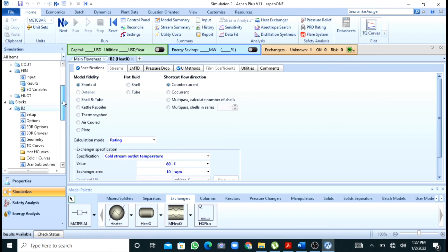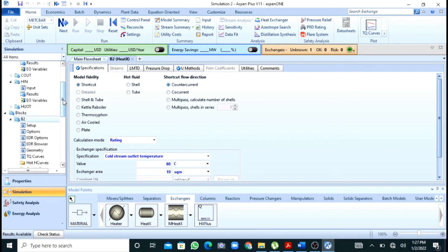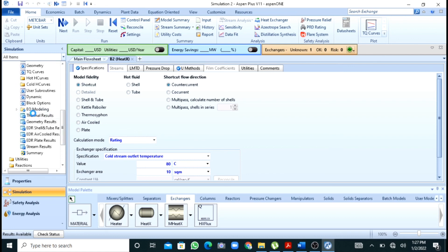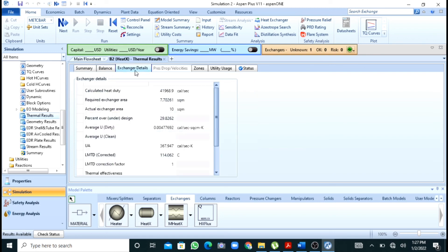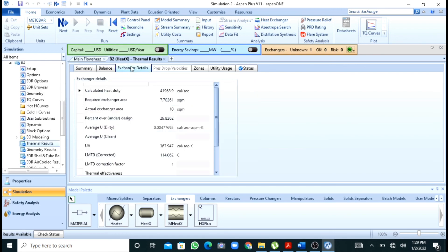The results are now available. I will press Thermal Results — you can see that the hot outlet stream temperature is 128°C. To find the required heat transfer area, I will press Exchanger Details. Here you can see the required exchanger area for this heat transfer to happen. The heat duty is also calculated and you can change units as required. I hope you liked the video.